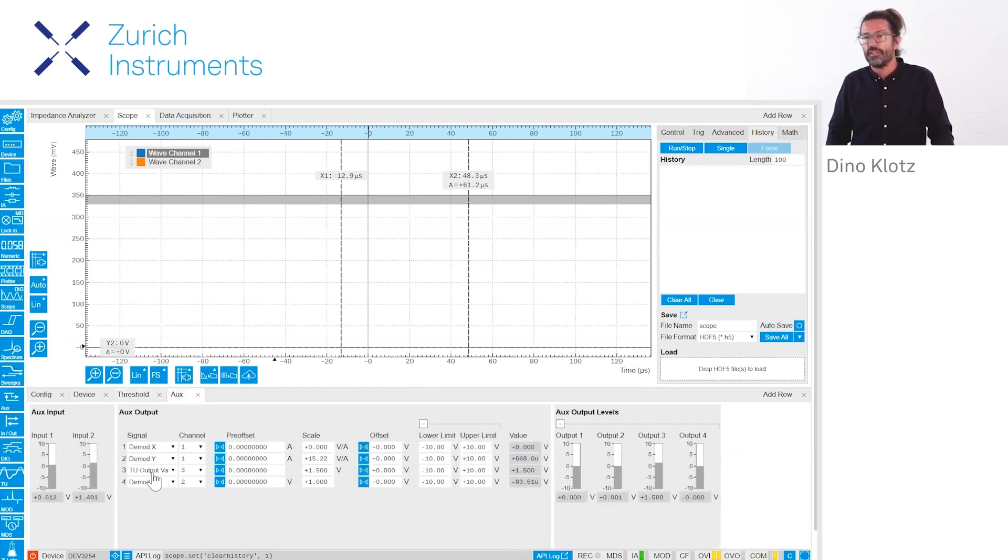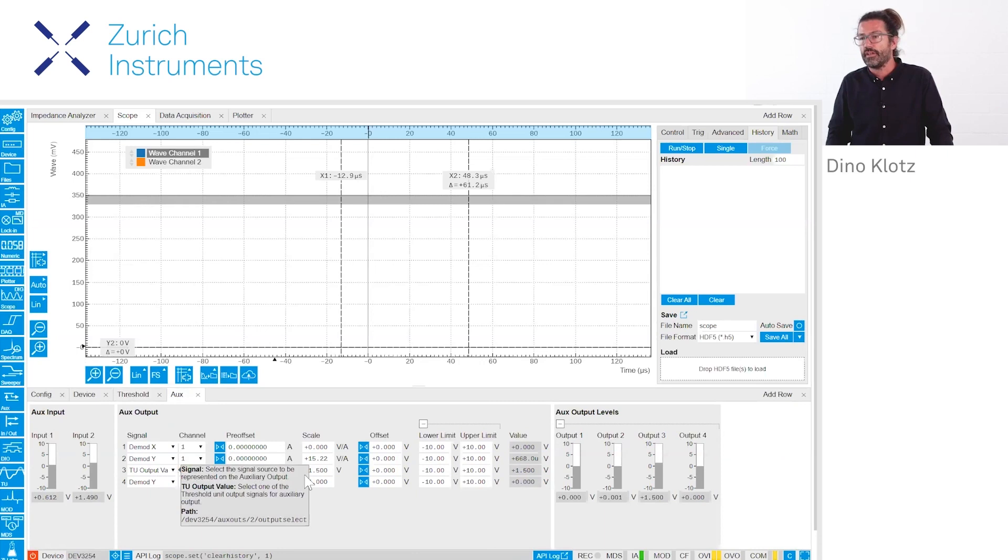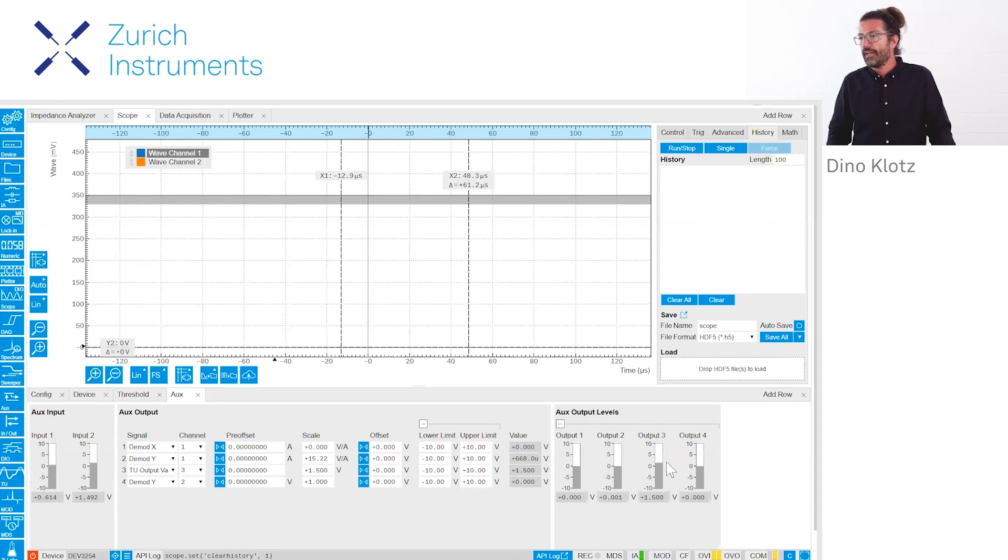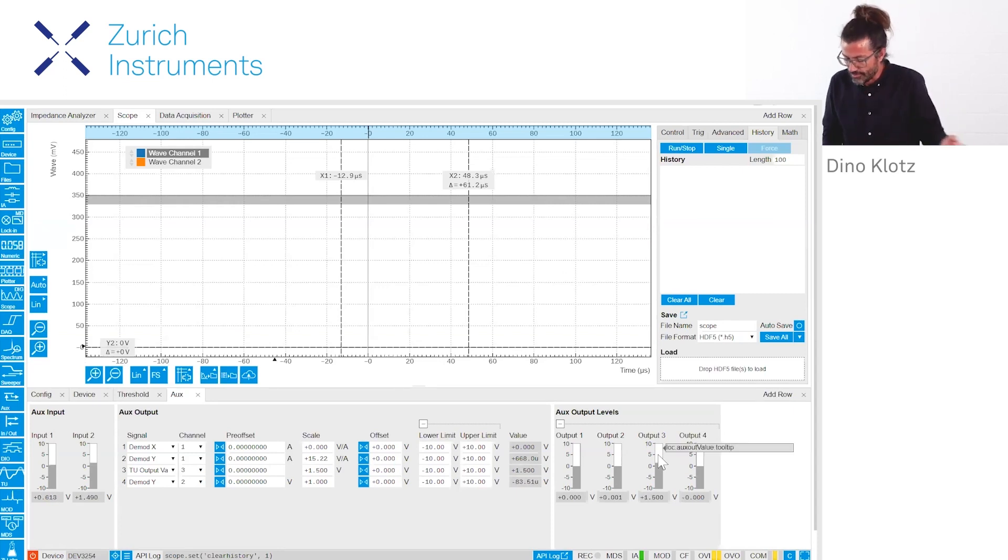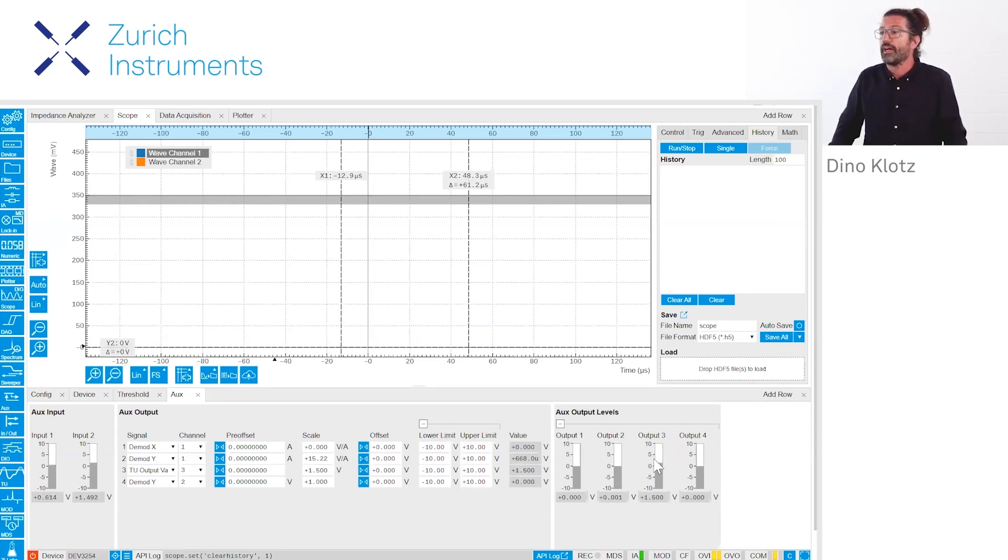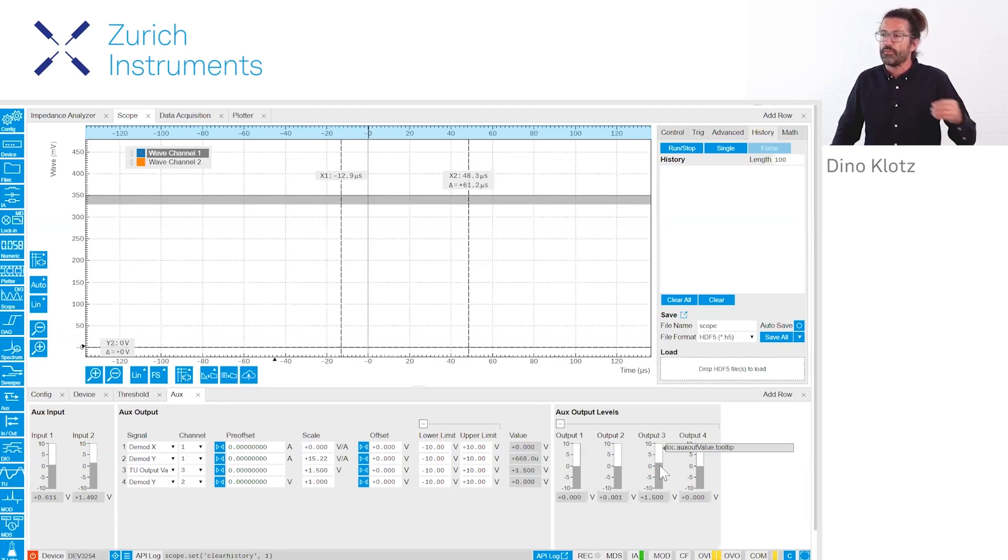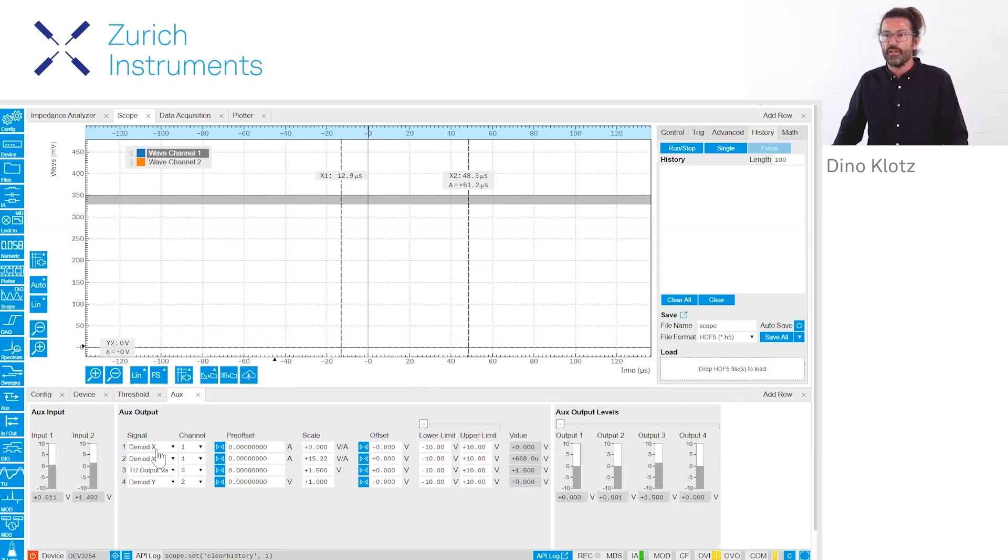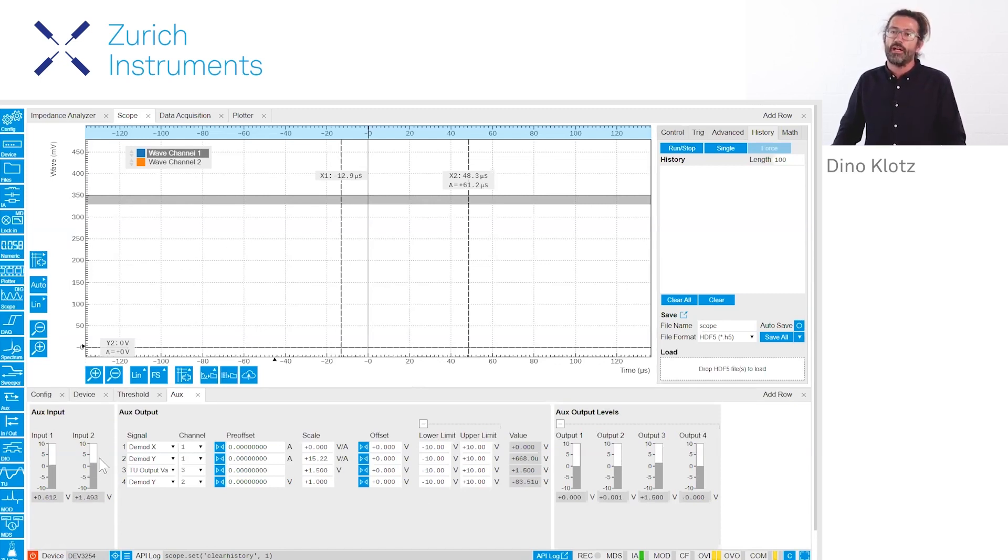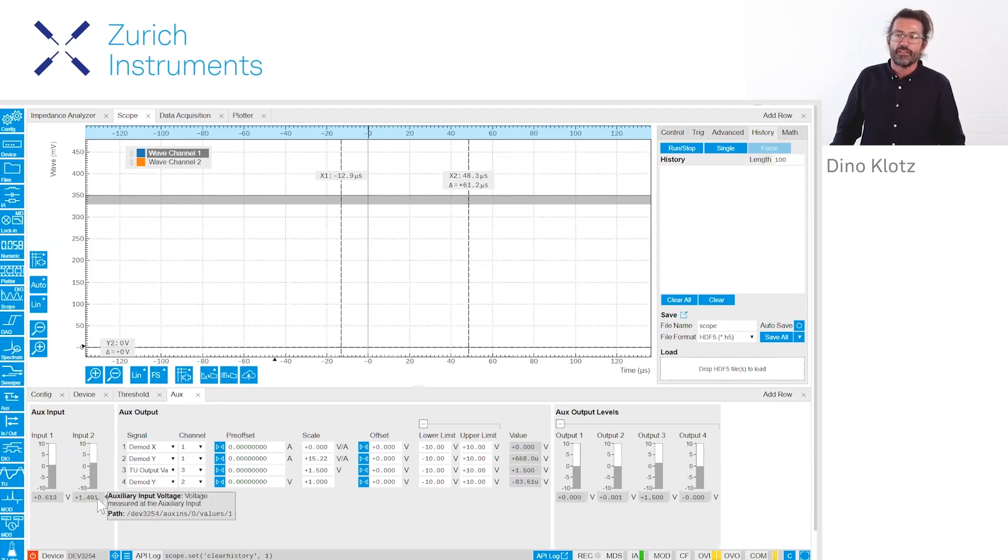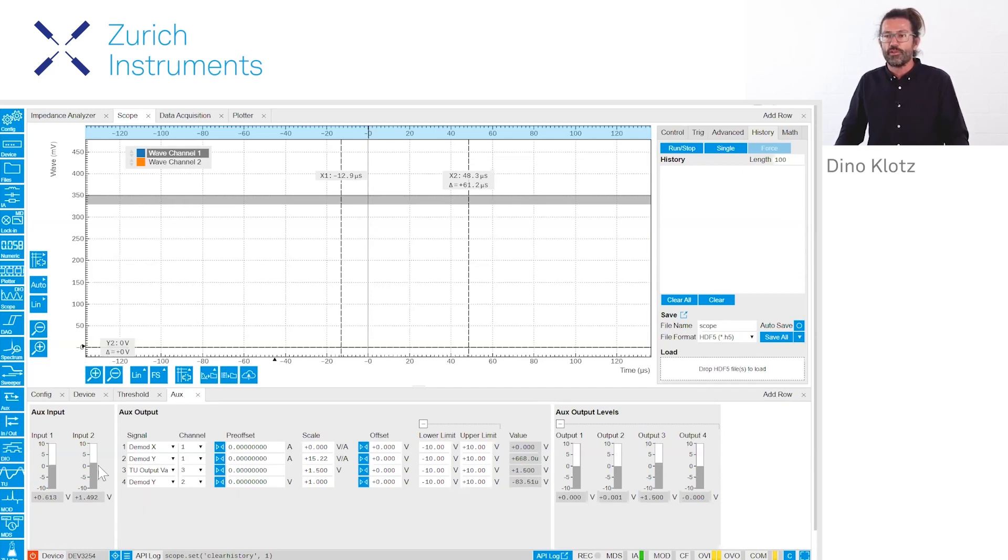I've configured it such that you see here on the output value that we have from zero to 1.5 volts an output, and you see it because it's connected to the output three. We see here on the output three that it's oscillating between zero and 1.5, and we're reading it again with the aux input two.